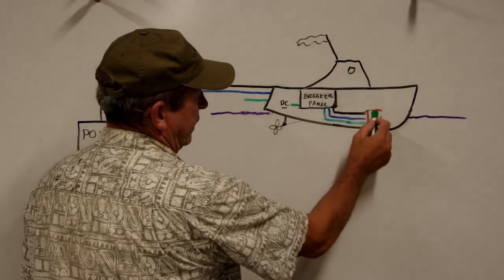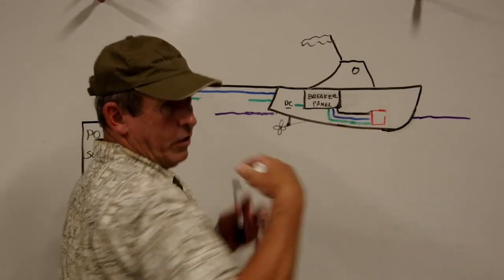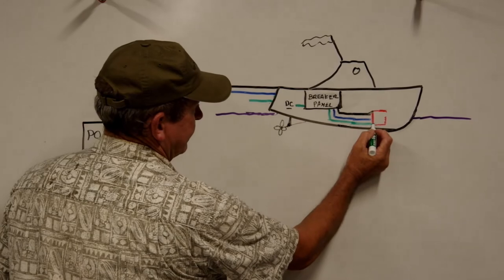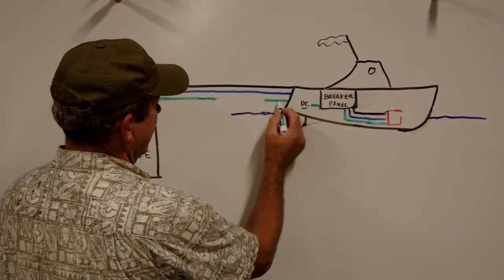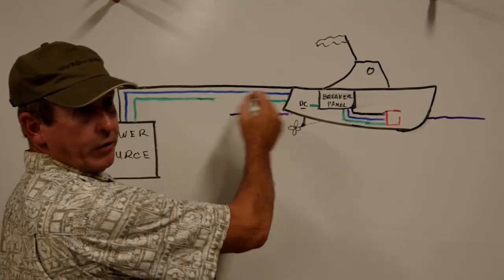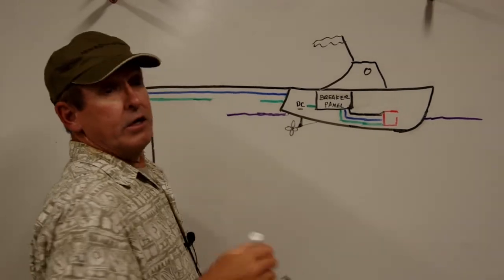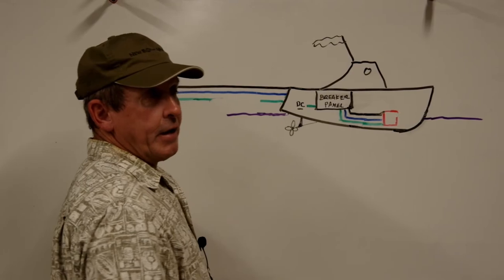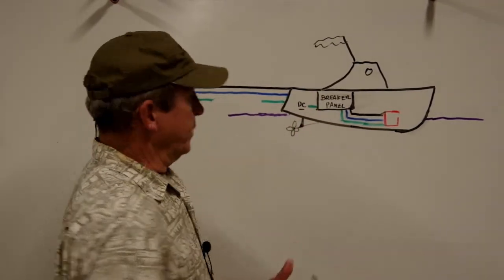Our line faults to the case of the chassis of our device — our device is now energized. Our fault current is going to travel along the AC safety ground and try to leave the boat by means of the shore cord, but it can't — that AC safety ground has failed. What that current is then going to do is find a path back to source through our boat's underwater metal.